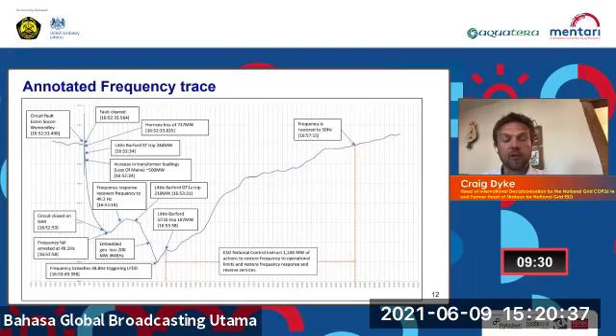The frequency response, which the control room have already instructed, is there to automatically react, and starts to bring that frequency back up, and it hits 49.2 hertz. We then see a gas turbine at Little Barford trip, which sees a further fall, coincident with what we found out through the investigation, that an additional 200 megawatts of generation also tripped at 49 hertz. The frequency then falls to 48.8 hertz, at which point the low frequency demand disconnection starts to kick in.